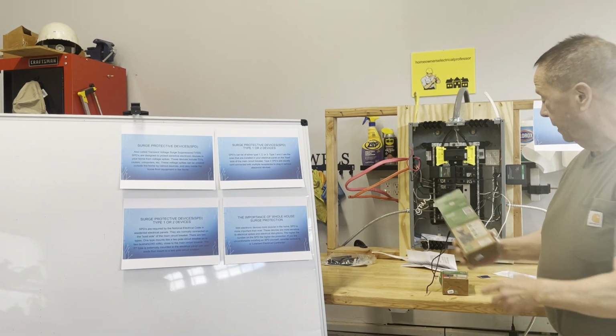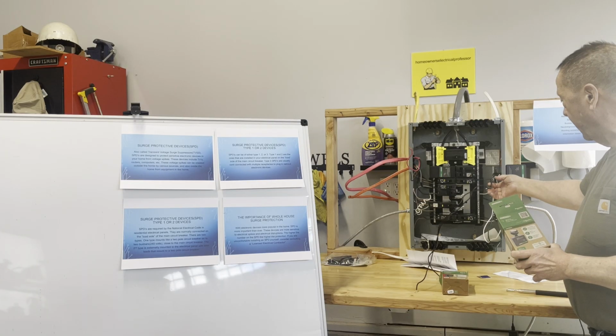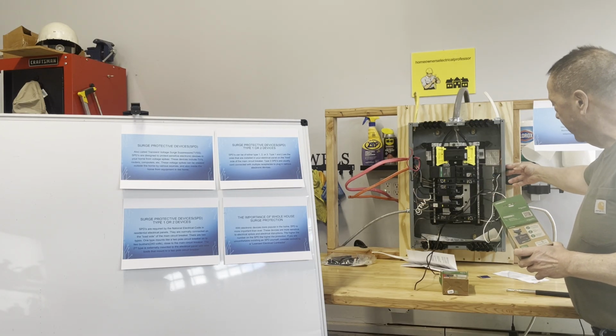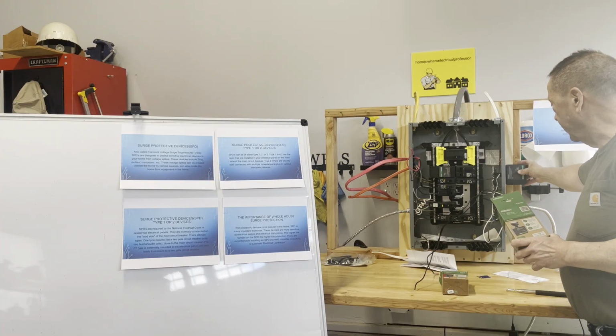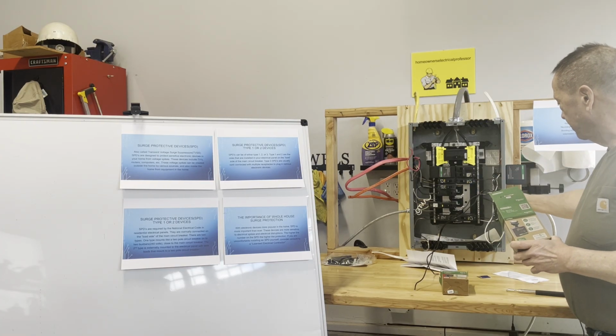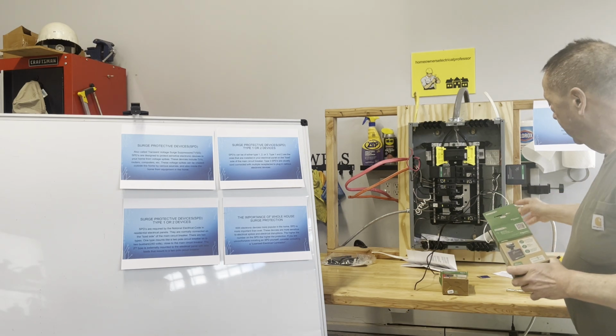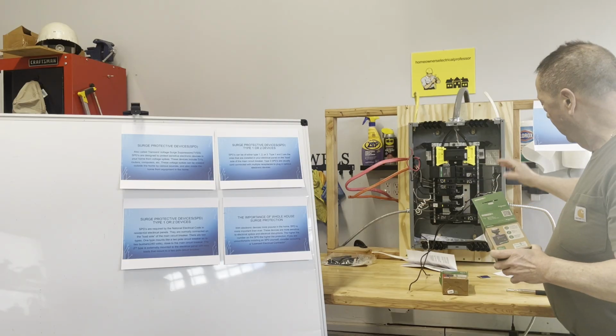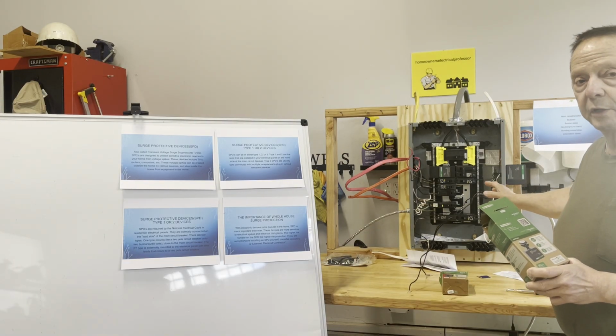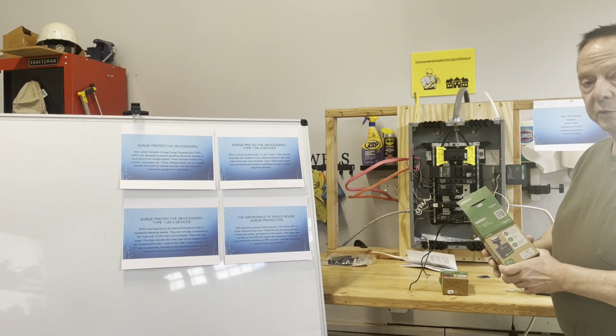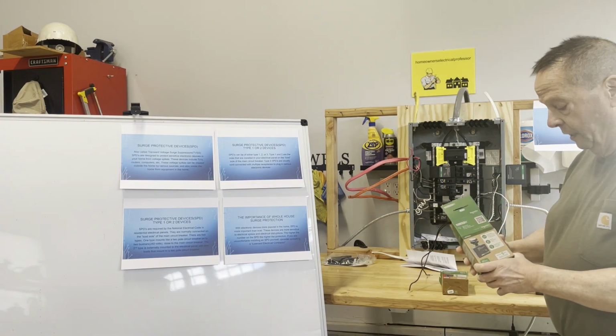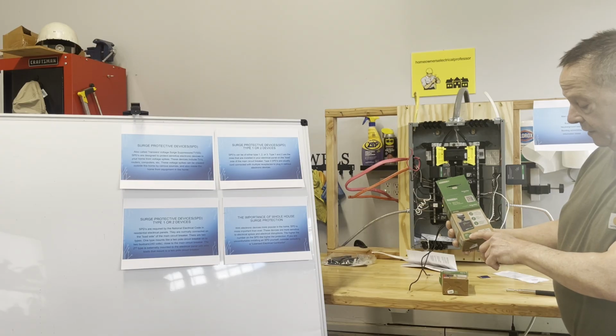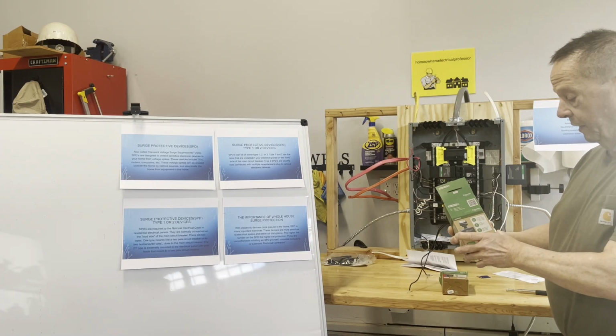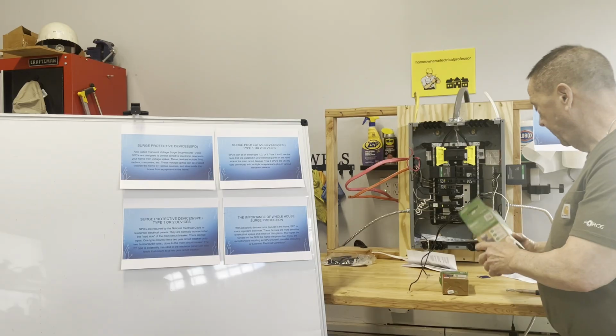Okay, I have two different types here. You can see the boxes. The one on the right hand side of the panel mounts on the panel with a couple of lock nuts so that it's securely mounted. As you can see, there's a white and a green that goes to your neutral bar, and there's also two black leads. Now, I didn't trim any of these down because I bought this and have another project in mind where I'm going to use it, so I'm just showing you what it looks like. This one here is rated for 80,000 amps of protection, the spike.